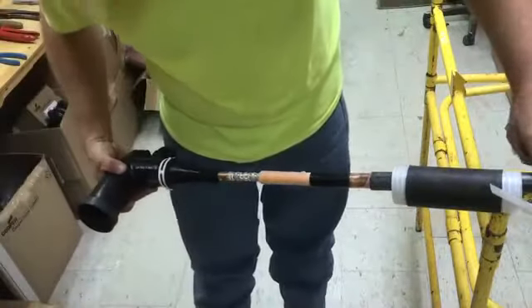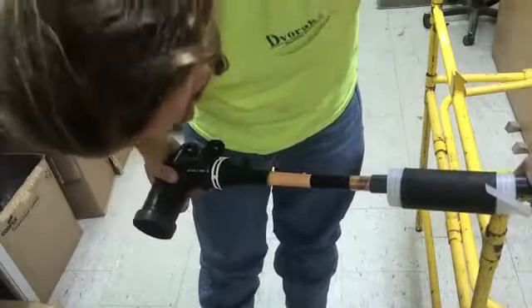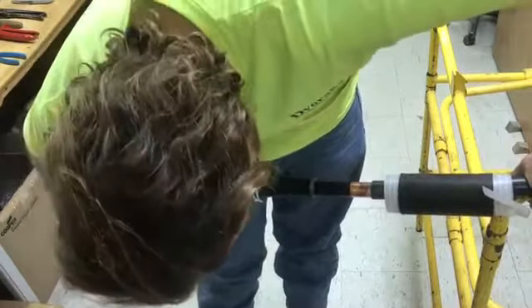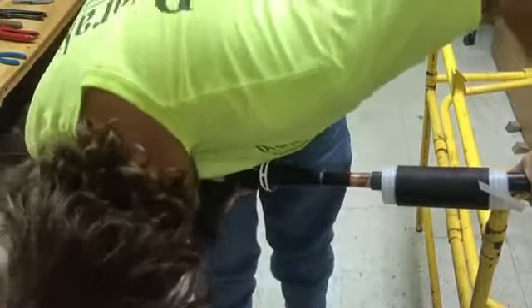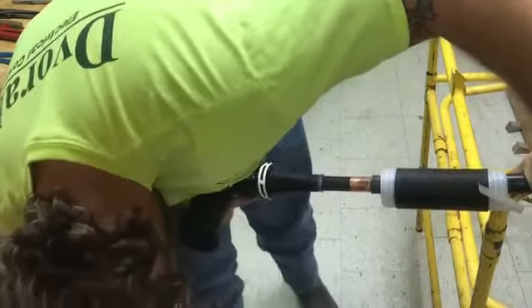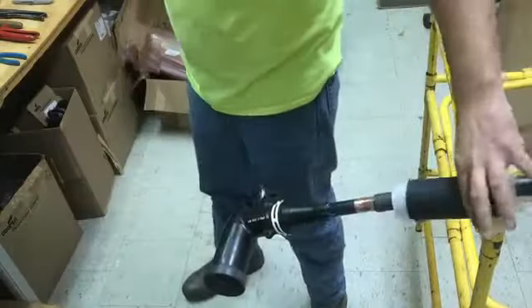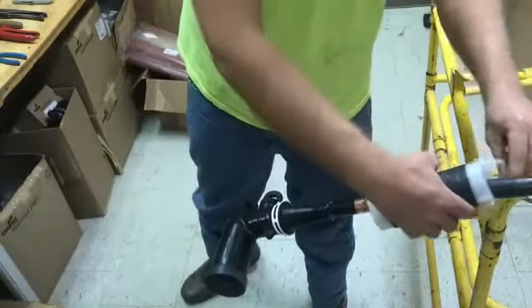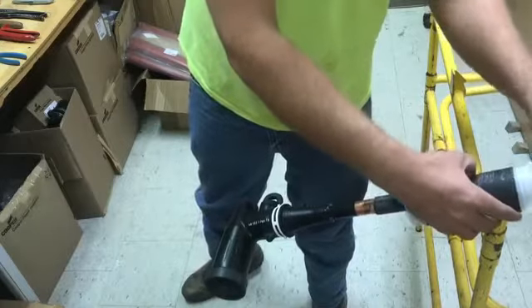I'll now install the 200 amp elbow. Before installing, ensure there are no sharp edges or burrs on the copper top. Install the 200 amp elbow facing the same direction as the threaded end of the copper top and push down until the copper top is seated fully inside of the 200 amp elbow.